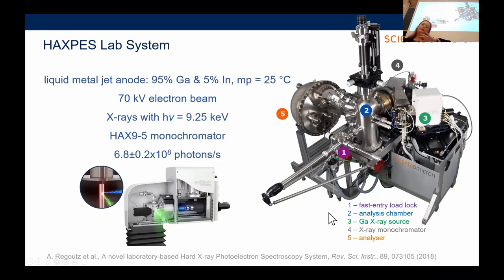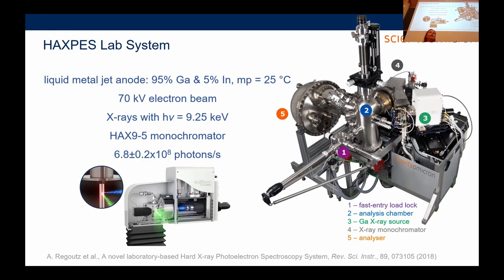The two main lab-based HAXPES sources available are chromium K-alpha (~6 keV) and gallium K-alpha (~9 keV), which you can now purchase commercially. Those suppliers will also sell you aluminium K-alpha, so in the lab you can now combine soft and hard X-rays in a single system away from the synchrotron. You can already see the number of HAXPES papers increasing and access for test measurements going up — a real change in pace and uptake of the technique.